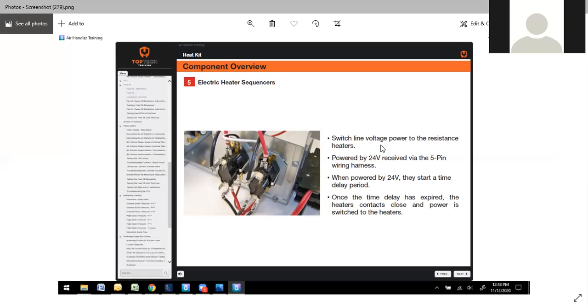Your sequencers switch the line voltage power to the resistance heaters, powered by 24-volt coils via the 5-pin harness. When powered by 24 volts, they start a time delay period. That way you're not bringing on all those elements at one time. So once it's energized, it starts a timing period. After the first timing period ends, it'll kick one sequencer in, then another, then another, then another.